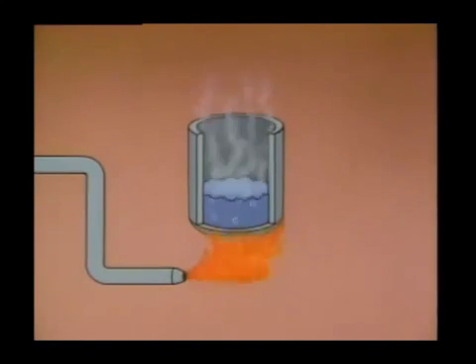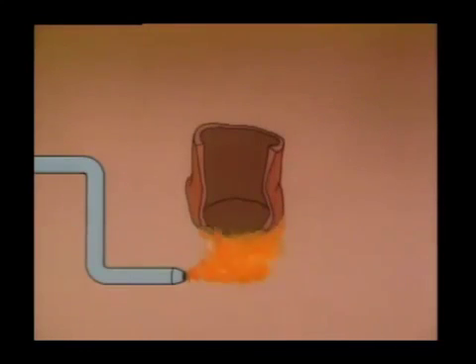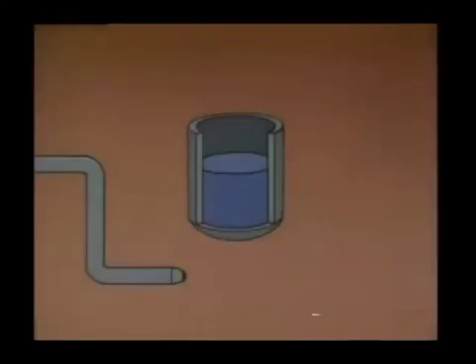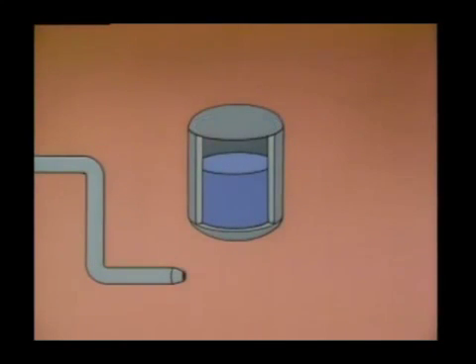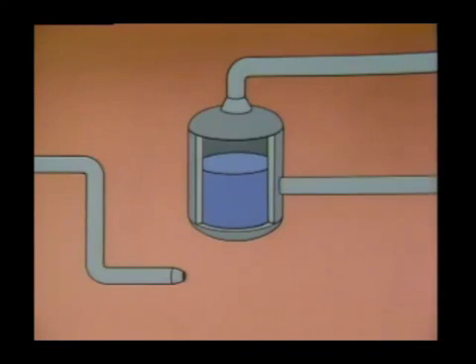In addition, as the water boils to steam, there's no way to replenish it. Without water, the shell could overheat and be damaged. So we'll have to make some changes. First, we'll cover the shell to prevent the steam from escaping. Then we'll add a steam outlet line to collect the steam and route it to where it can be used. We also need a way to supply water to the shell so it won't boil dry, so we'll add a feed water line. It will provide a continuous supply of water to replace the water that's changed to steam.